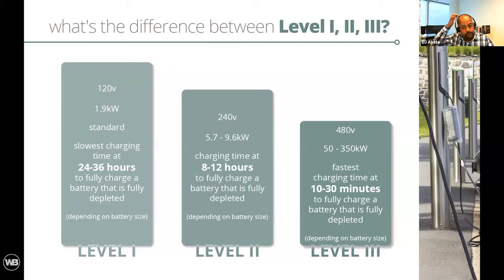Got it. Yeah, and I'd say also, my house has a decent electrical panel, a 200 amp at 240 volt. And even that whole panel isn't going to get you to the lowest threshold on that fast charger. These are orders of magnitude bigger than what you're looking at in a standard home. So that 350 kilowatts, like 600 amps at 480, that's at 480, right? Your building only has 240 volt. So if you were to do it at 240, we're talking about a 1300 amp breaker.